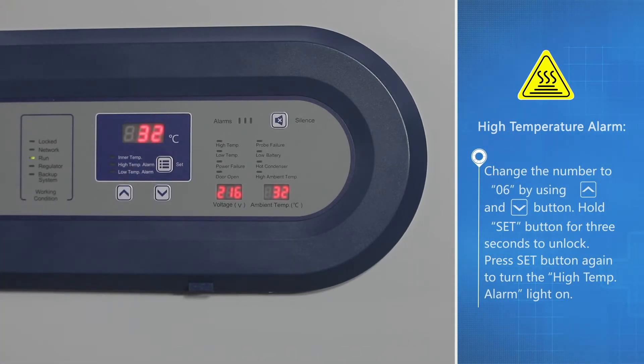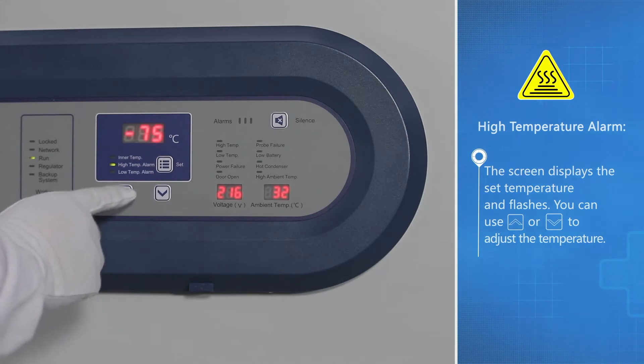High-temperature alarm: change the number to "06" by using the up button and down button. Hold the set button for three seconds to unlock. Press the set button again to turn the high temp alarm light on; the screen displays the set temperature.